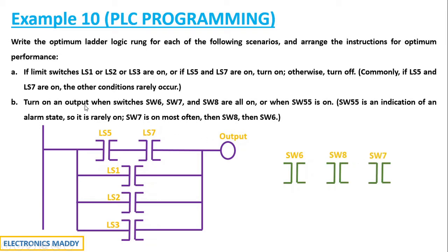Output is high when all of these switches are on together. That means it should be an AND gate and we have an OR gate because they have mentioned OR when SW55 is on. SW55 is an indication of an alarm state, so it is rarely on. Whichever rarely occurs, let us place them in the bottom. You don't have to go through each of the rung conditions. Once if the first rung is high and if it can determine the output then you don't have to check for the second one.